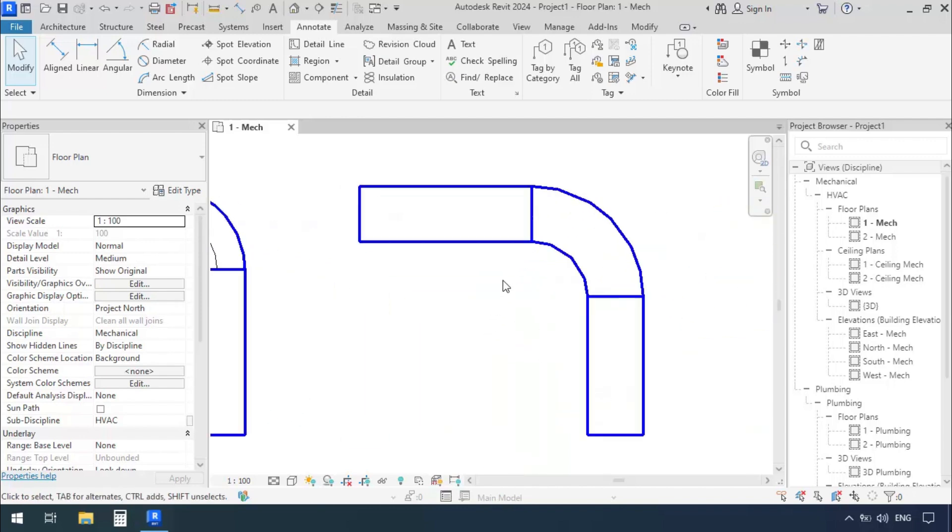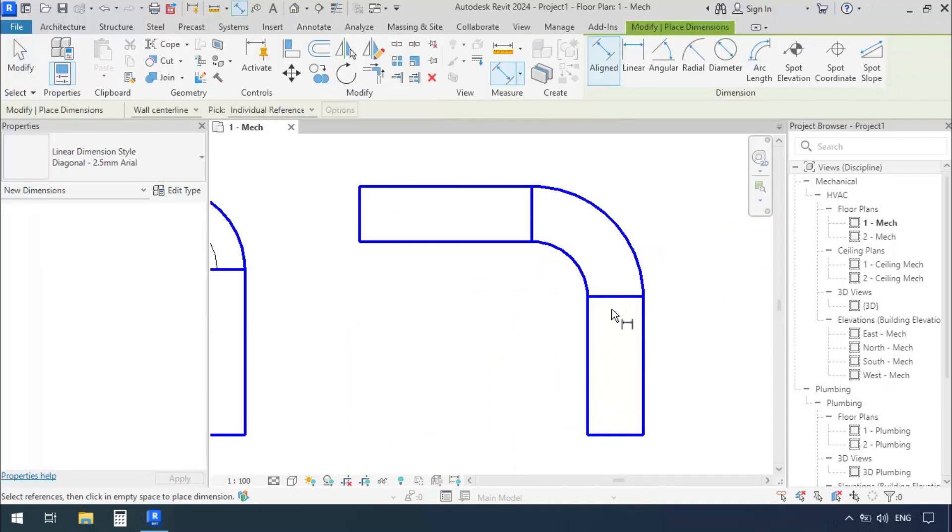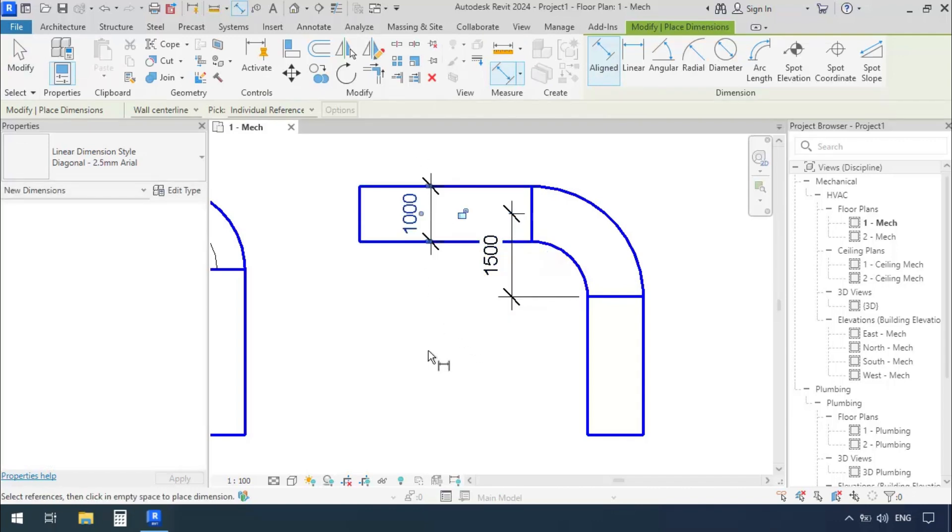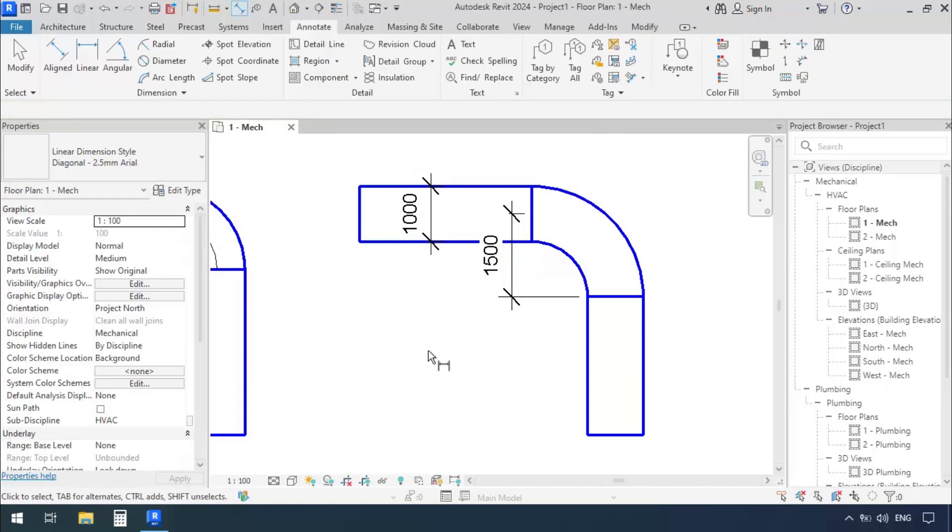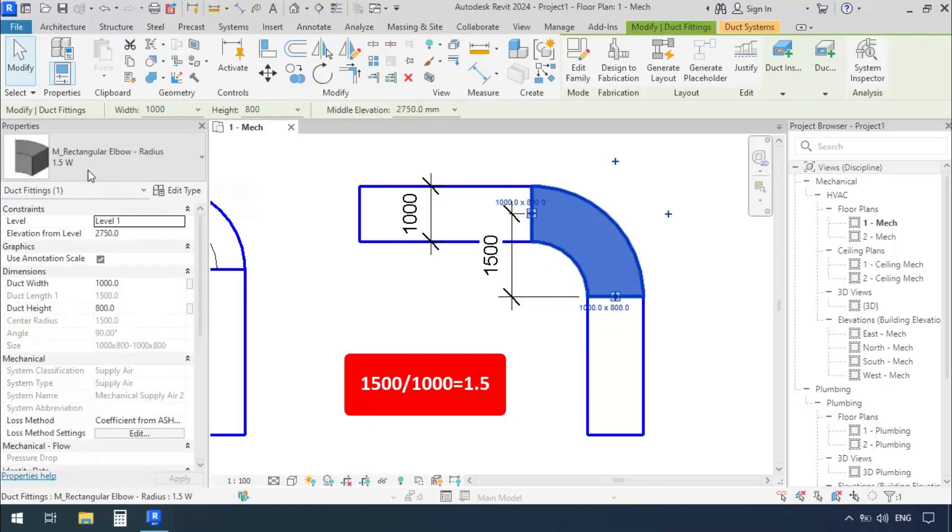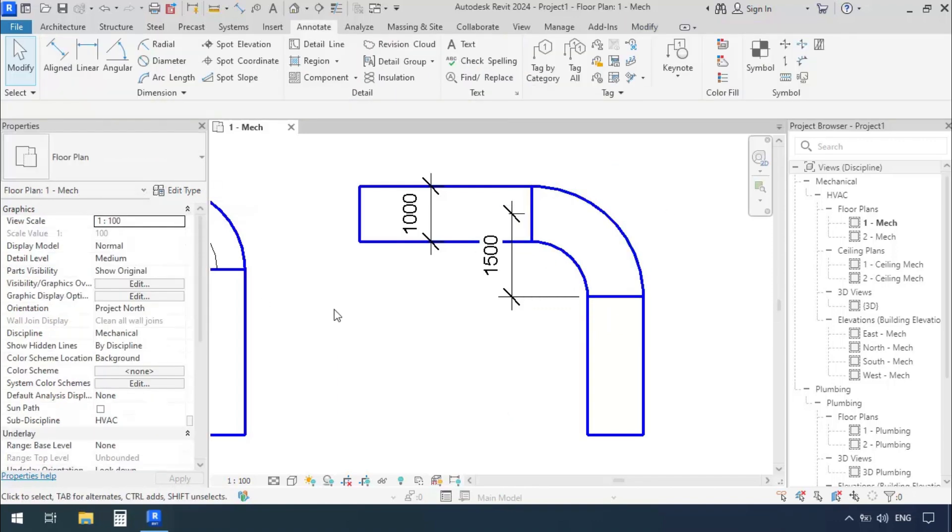Let's check out the next one. We'll measure it using Align Dimension. First click, then the second click here. We got 1500. The width of the duct was 1000. So 1500 divided by 1000 equals 1.5. The radius of this elbow is 1.5 times the width of the duct. So it's 1.5W.